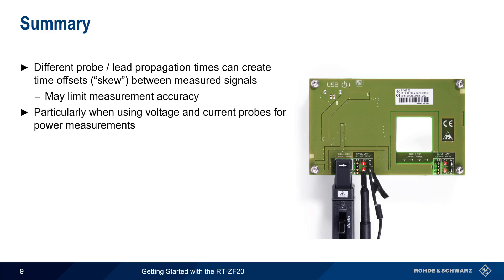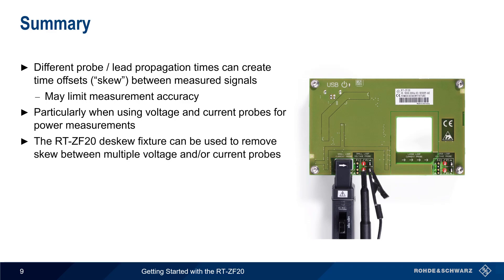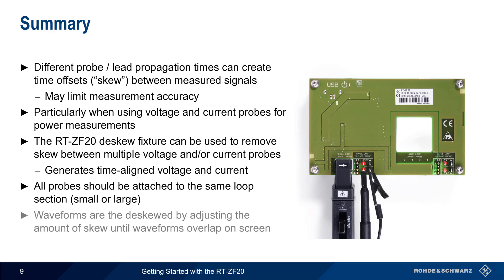Let's end with a brief summary. Different propagation times on different oscilloscope channels can lead to time offsets between measured signals. These offsets can limit measurement accuracy, and this is particularly true when using a combination of voltage and current probes for making power measurements. The RTZF20 power de-skew fixture can be used to remove skew between multiple voltage and/or current probes by generating a signal with time-aligned voltage and current. Both the voltage and current probes are attached to one of the two loop sections, and then the time offset or skew between the displayed waveforms is adjusted on the oscilloscope until the waveforms overlap on screen.